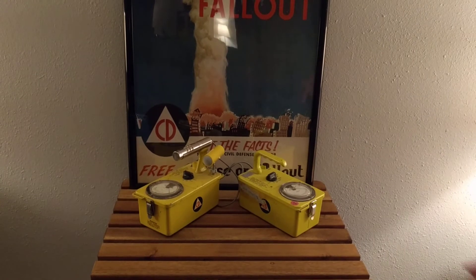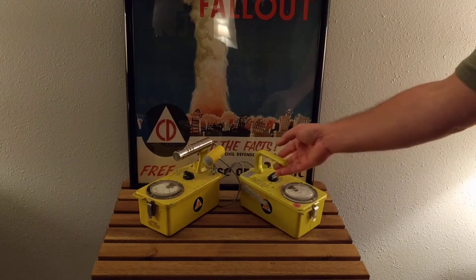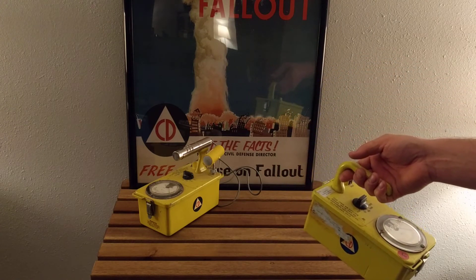This device right here is called a CD V-715. This is a high-range survey meter. If this reads anything, it's either broken — because it reads in roentgens per hour — or a nuclear bomb has just gone off, or you're at the site of a nuclear meltdown and things are about to get very bad for you.